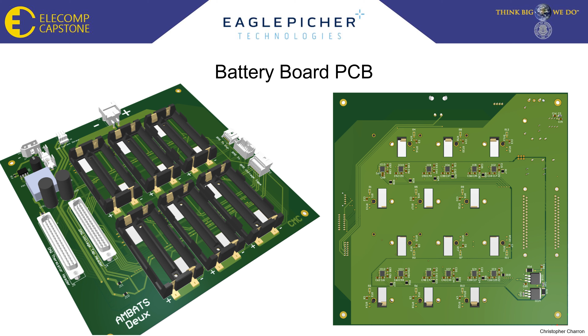This is far above the voltage specification of the data acquisition unit, so we use differential amplifiers to remove the common mode voltage and measure the cell voltages with respect to ground. The output of the differential amplifier is fed through a burden resistor for measurement, which is needed because the DAQ inputs are high impedance. A differential amplifier circuit is needed for every cell to ensure consistent measurements.